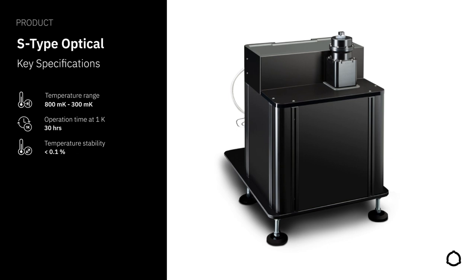The sample stage has a diameter of 41 mm and offers enough space for a stack of piezo positioners. With our optional low resistance wiring, the positioners can be operated over the whole temperature range from room temperature down to below 1 Kelvin. For high frequency measurements, up to 4 RF lines can be added.